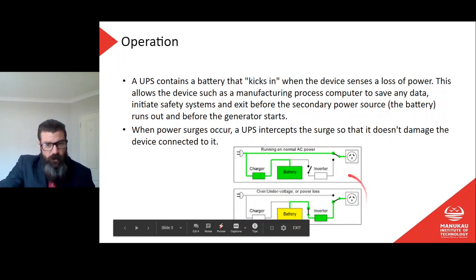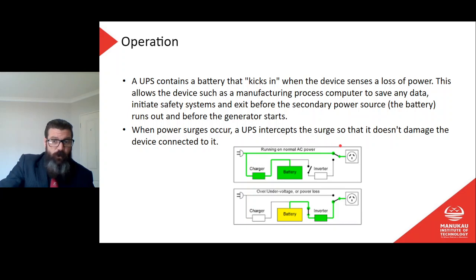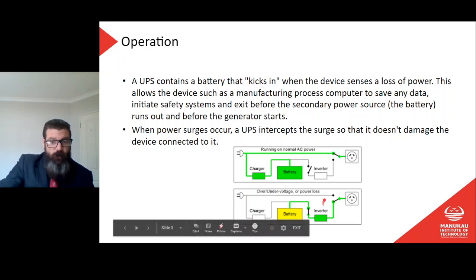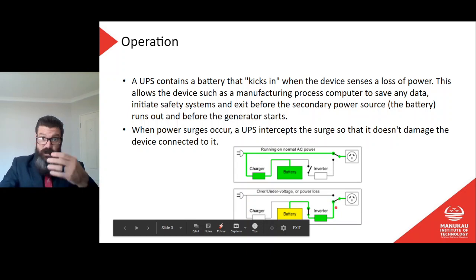When we lose voltage on the input, so now our main supply is lost, then we have nothing running through here, nothing running into the charger, we've got no mains. This switch automatically switches over. It would usually run off a contactor. So if we had a relay coil powered off here, then when the power's on, the relay coil is switched on, and that would hold that contact there. When the power switches off, that relay coil is de-energized, so the switch drops out and falls into this position here. That's the most basic level of automatic changeover switch.